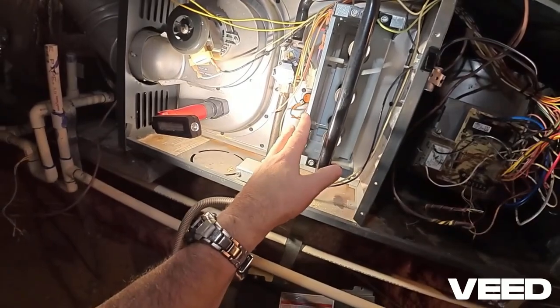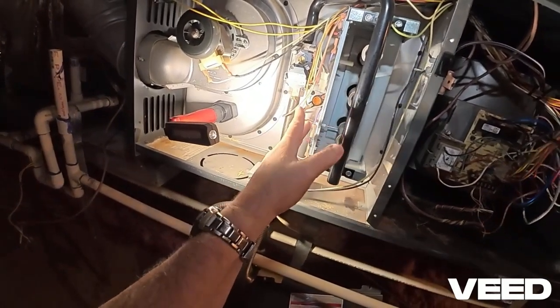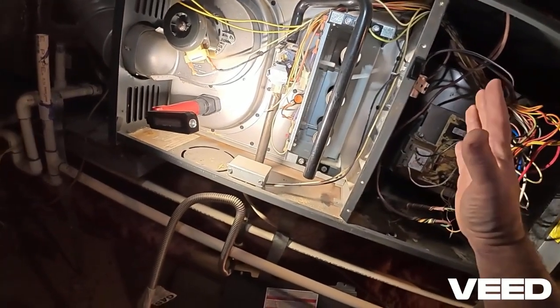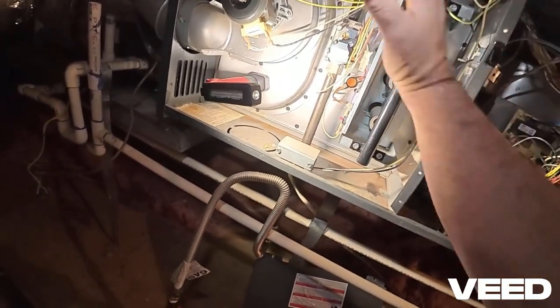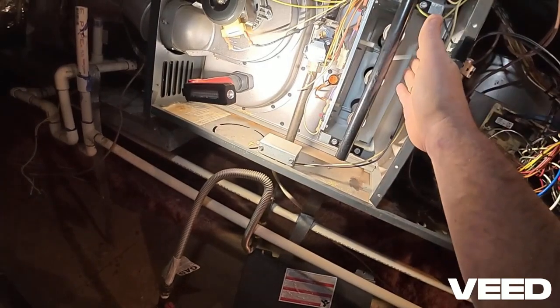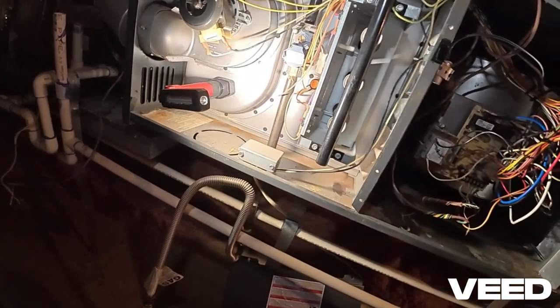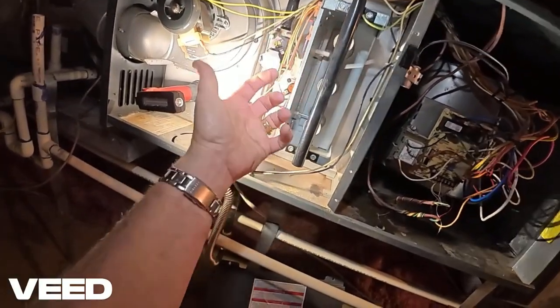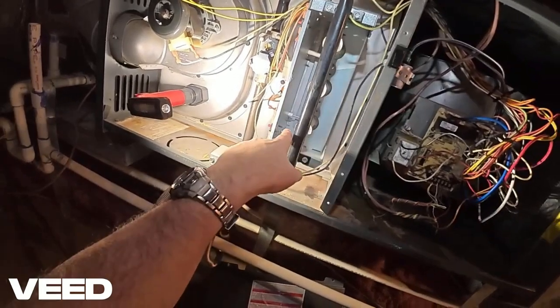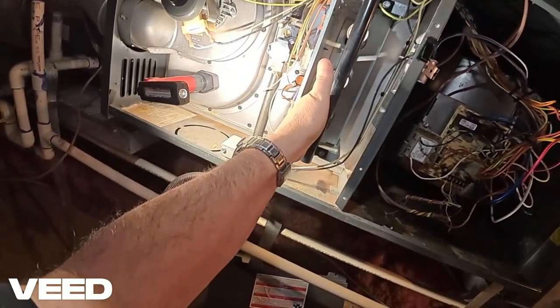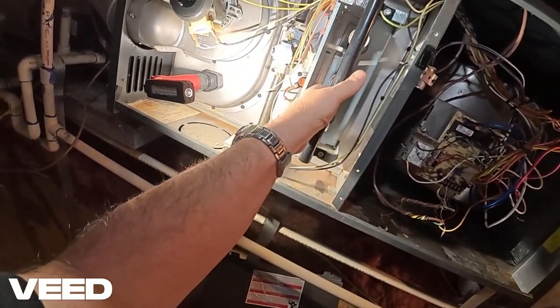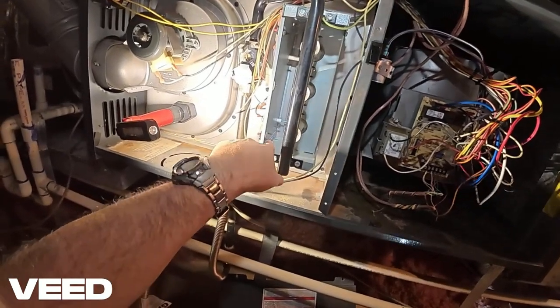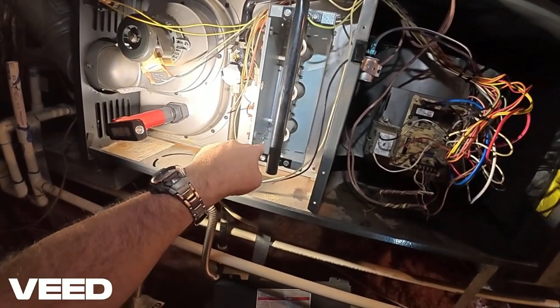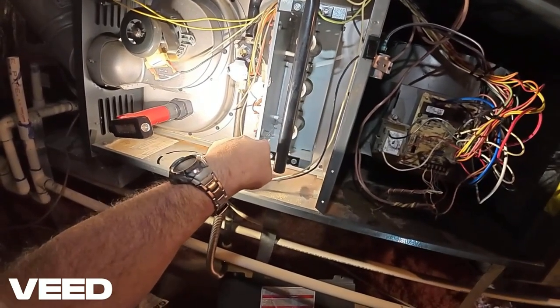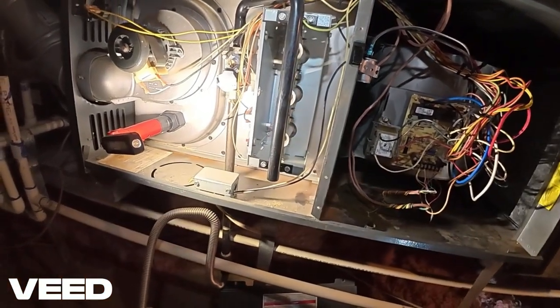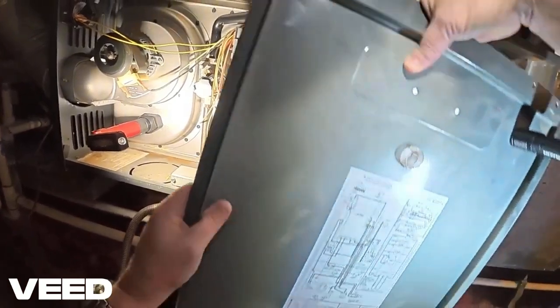And it could be a problem with your heat exchanger. For example, if there's a hole or a crack in the heat exchanger, when the blower motor turns on and is blowing air across the heat exchanger in the back, if there's a hole in there, it will actually blow this flame backwards. And it could be an issue as well with the burners and these orifices in here, but that's a pretty serious issue and not something that you want to play with, and you need to really call in a professional and look at it. But that's the rollout and what those could be pointing to.